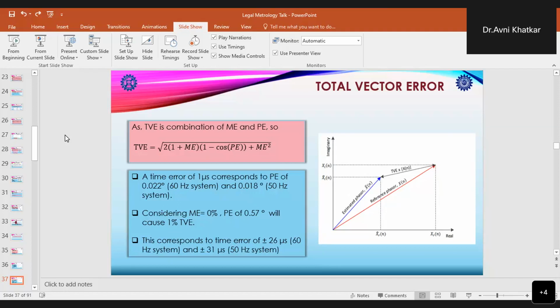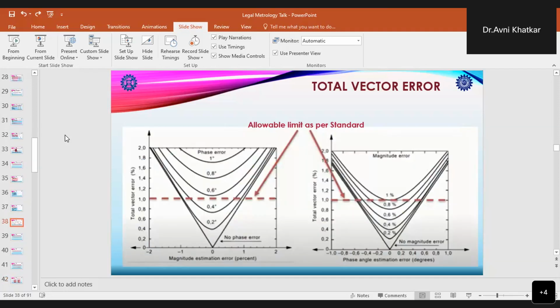A time error of 1 microsecond corresponds to a phase error of 0.022 degrees in a 60 hertz system and 0.018 degrees in a 50 hertz system. If we consider that magnitude error is 0%, a phase error of 0.57 degrees will cause 1% TVE, which is the maximum allowable TVE as per any standard. This corresponds to a time error of plus minus 26 microseconds for a 60 hertz system and plus minus 31 microseconds for a 50 hertz system. In the first figure we have the magnitude error estimation. If we have no phase error, then as per this graph we can see how the total vector error changes as the phase angle increases. Similarly, in the second figure, there is no magnitude error at the 0 point, and as it increases, the allowable limit as per standard is 1%. So total vector error can be maximum up to 1%.